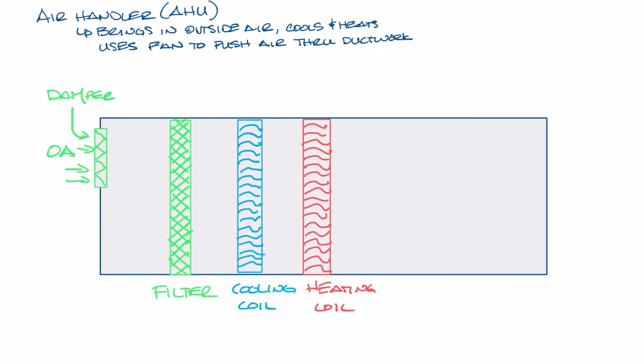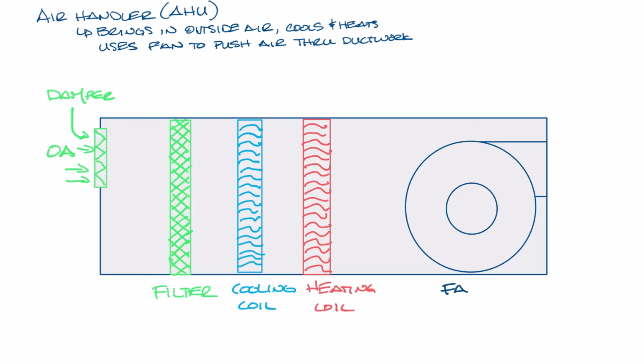Air handlers also need a fan. Air handlers can have the fan before or after the coils. If the fan is before the coils, it's called a blow-through arrangement because the air is blown through the coils. And if it's after the coils, it's called a draw-through because the air is drawn through the coils. Draw-through units are more common than blow-through units. After the fan, the air leaves the air handler and goes into the ductwork. So at minimum, with a filter, coils, and a fan, you have a simple air handler.